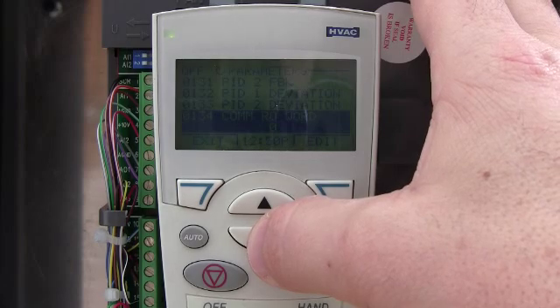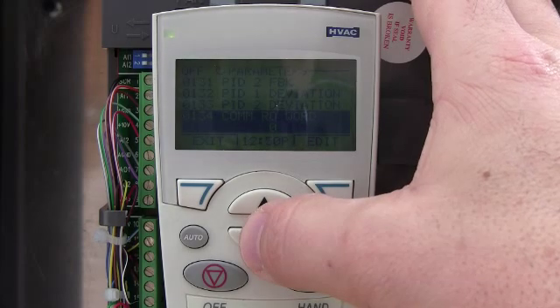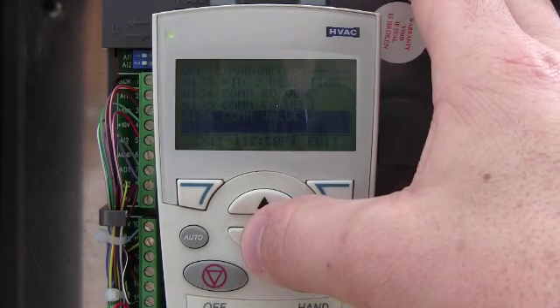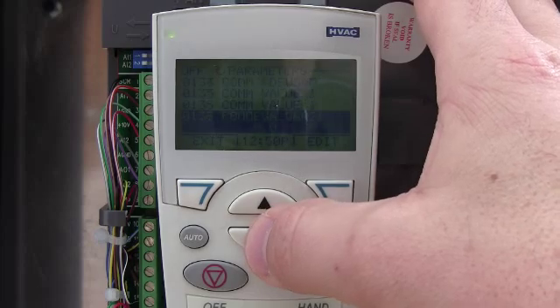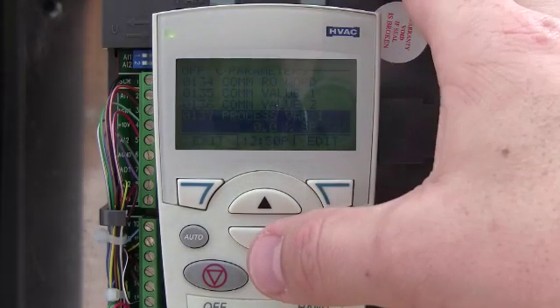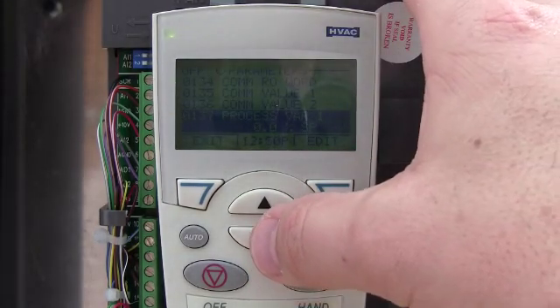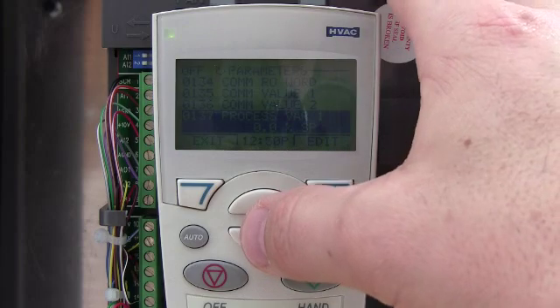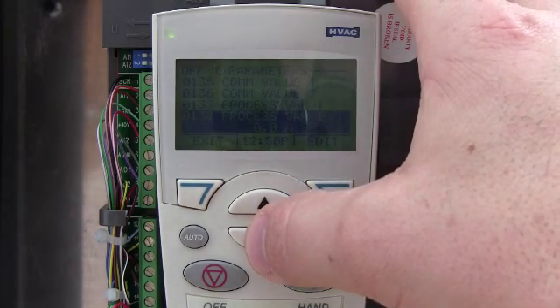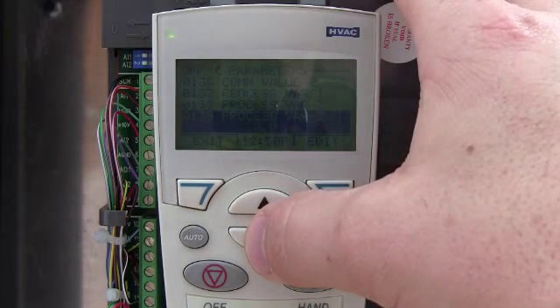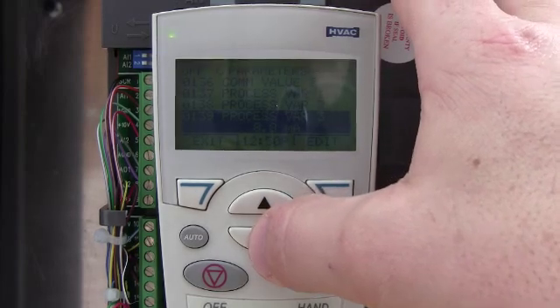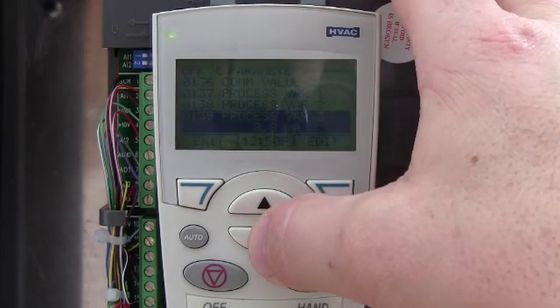The deviation is basically how far offset the drive is from what you have it programmed for. So you have PID one and two for deviation. Your control com word, com value, com value two — that's off of this bottom port for your communication, typically. Process variable one and two — these are programmable inputs. This is basically your main display.